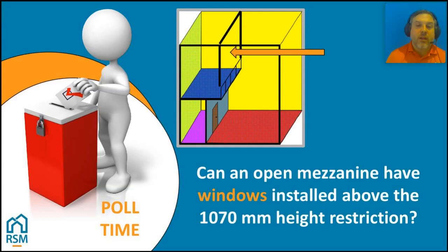And so some people say, well, okay, maybe we can have these windows. But you know what? I think there could be a little bit of controversy on this question. But based on my interpretation, it says it's within an open room. And the smell criteria, I can't smell it. I might not hear as well with windows. So I think the safety net of having this open is pretty important. And windows are something that would likely remove that, or not have a big enough impact to ensure the safety of that open mezzanine.